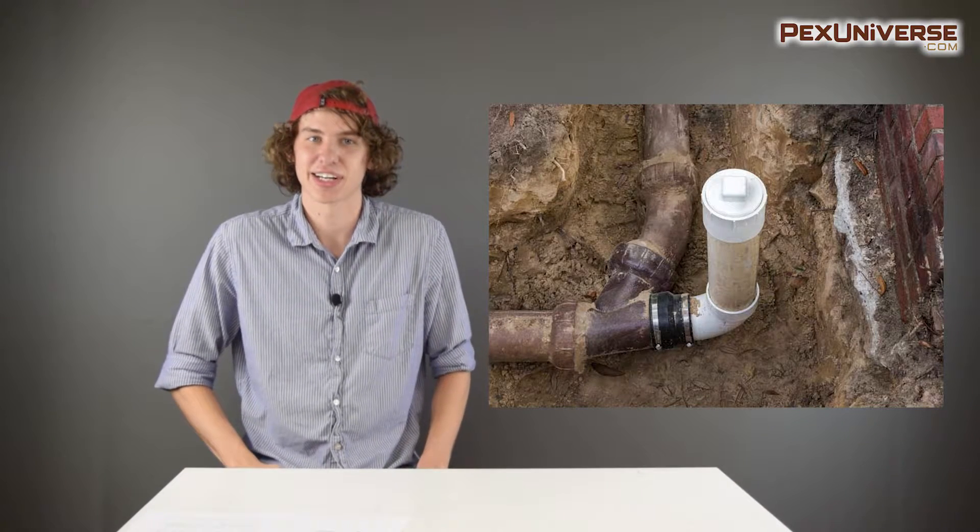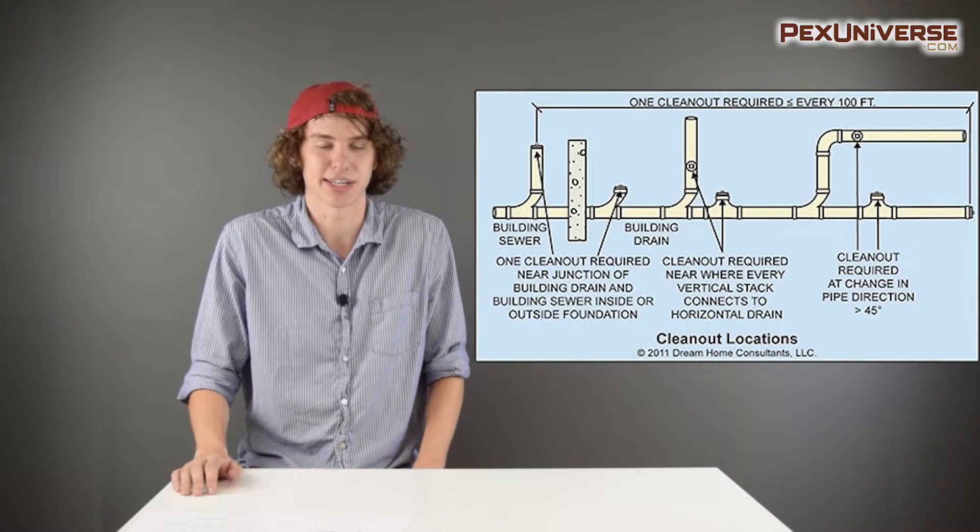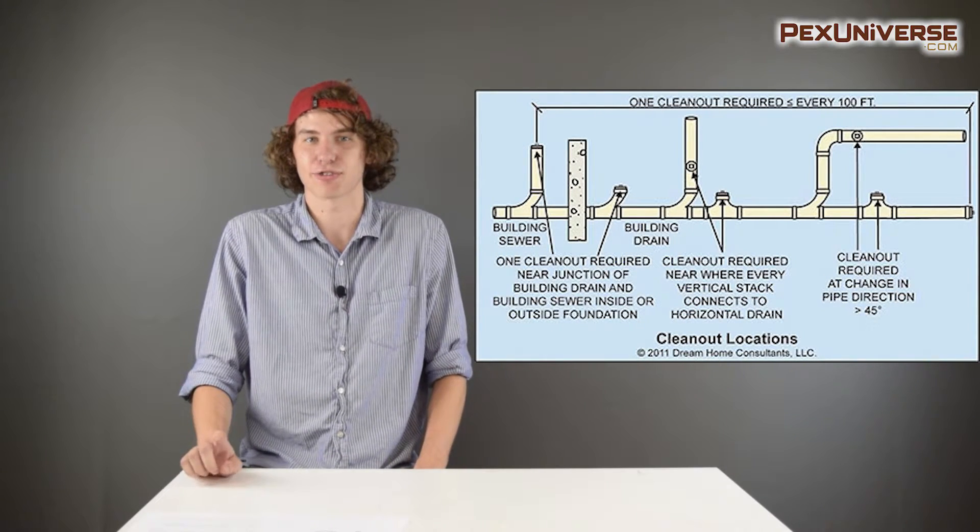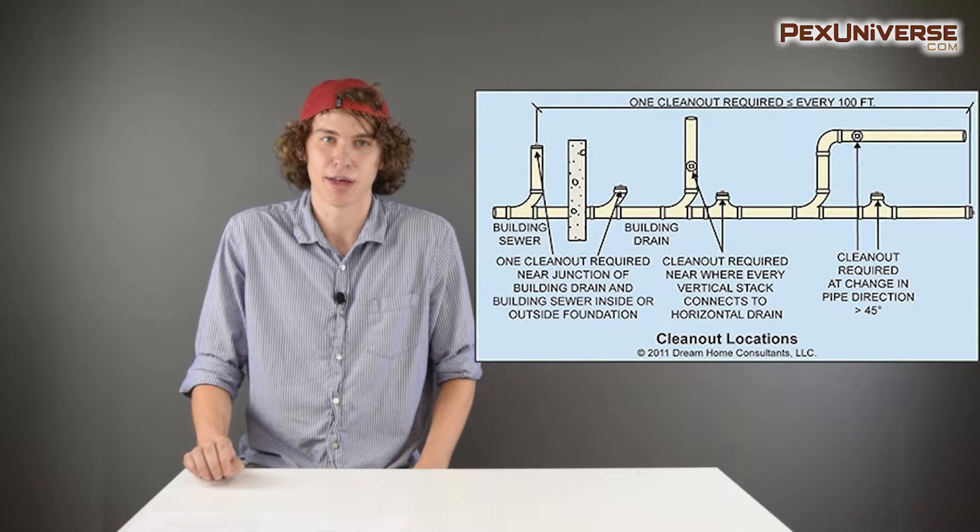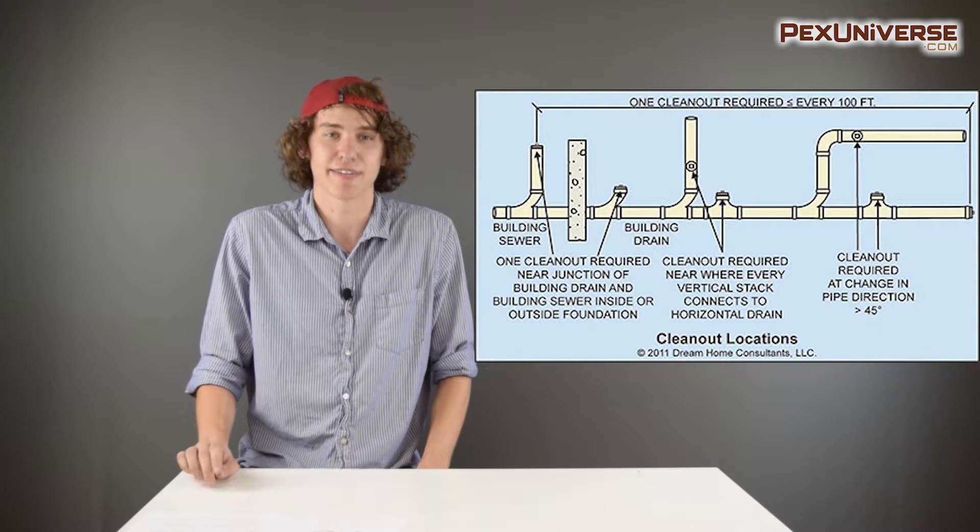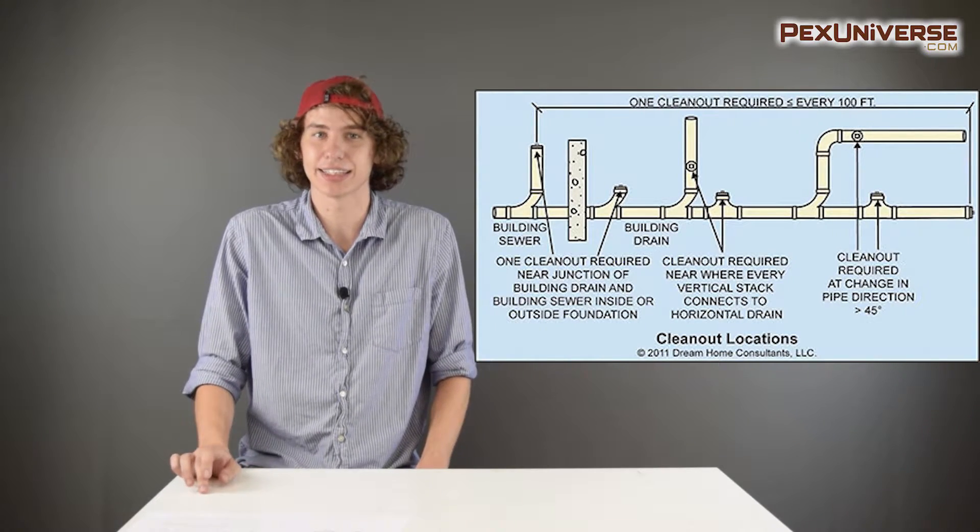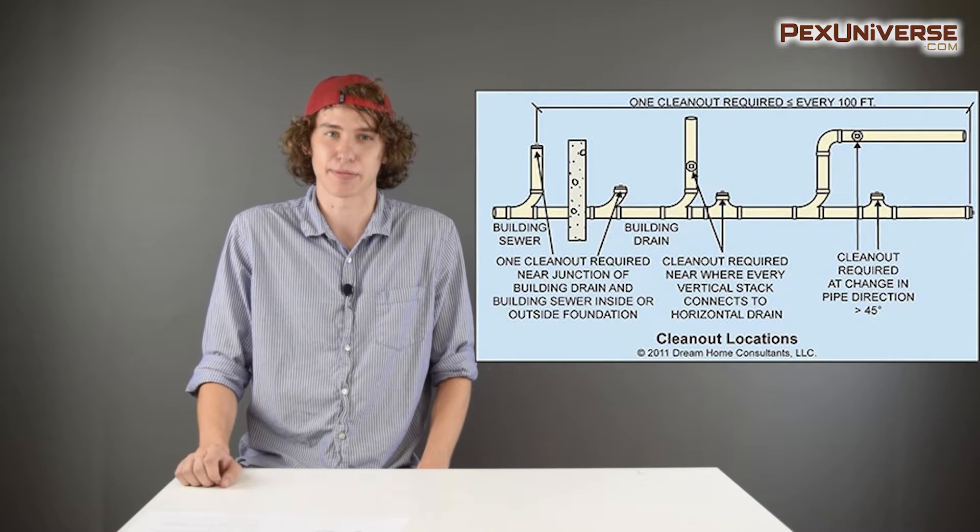First off, cleanouts. If you haven't heard of them, you're definitely doing something wrong. Cleanouts provide access to your drainage pipes in case of blockages. Every drainage pipe must have a cleanout installed minimum of every hundred feet, and every cleanout must have a clearance of about 18 to 32 inches depending on the size of the pipe. There are a lot more specifics about cleanouts, and again you can find all those in your state's specific code.